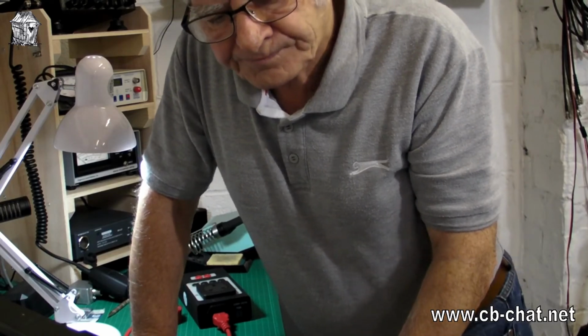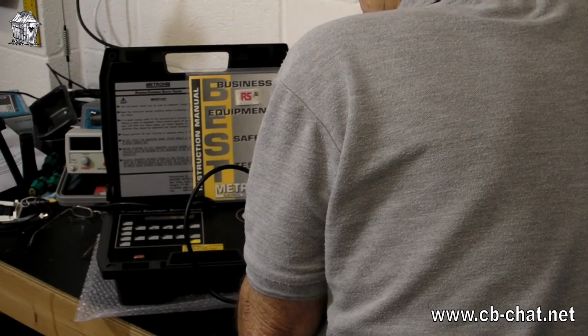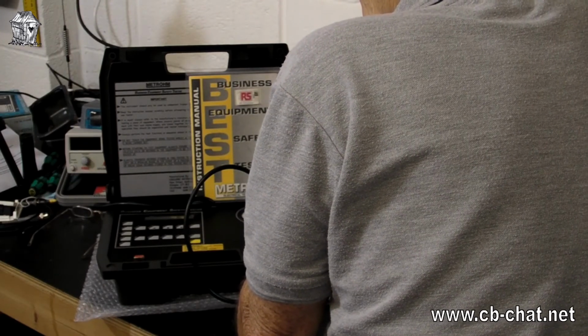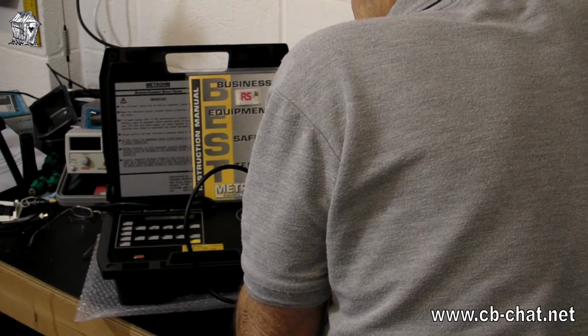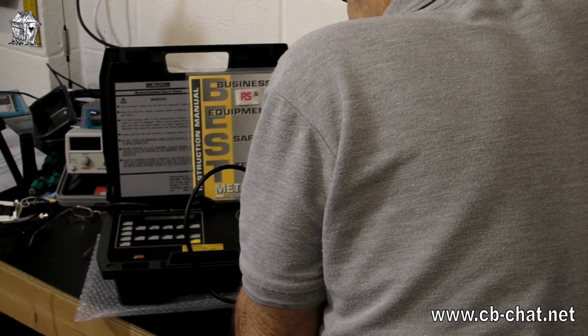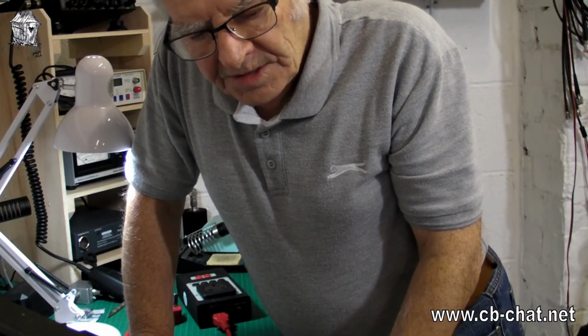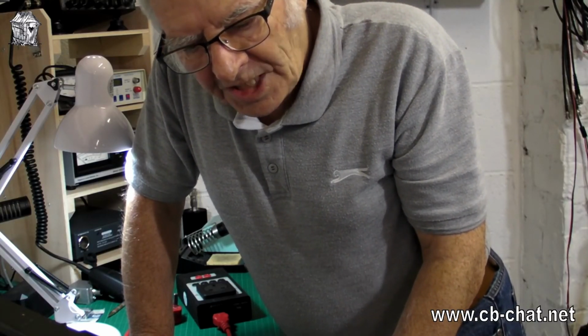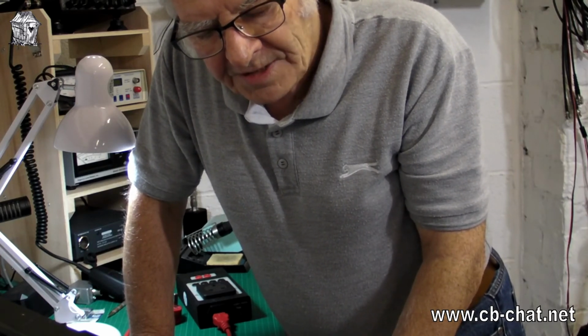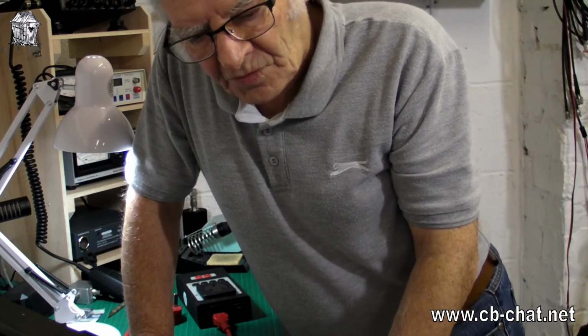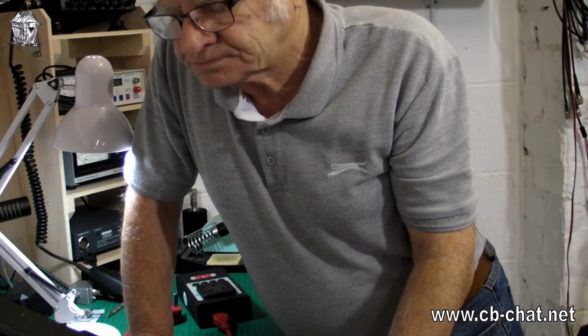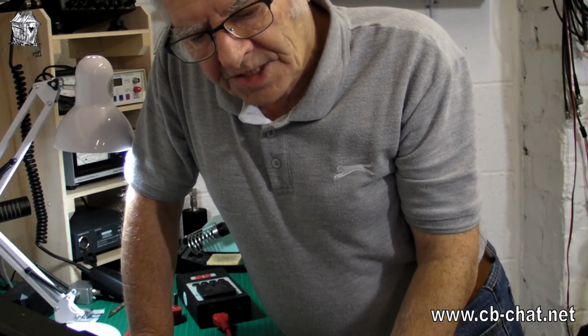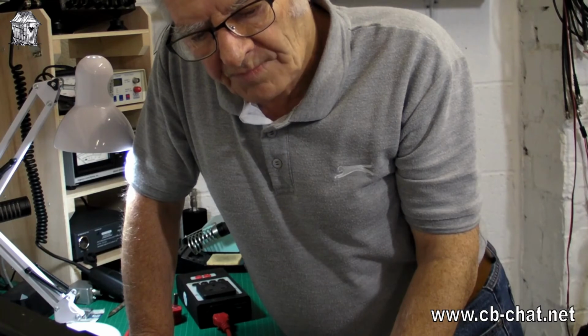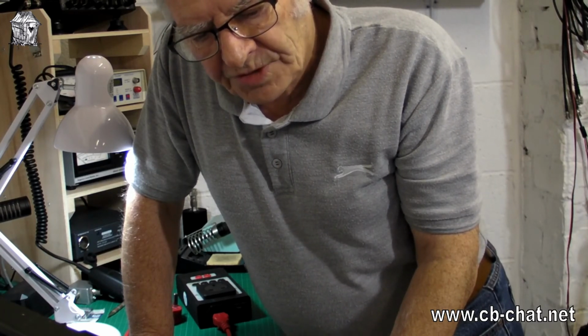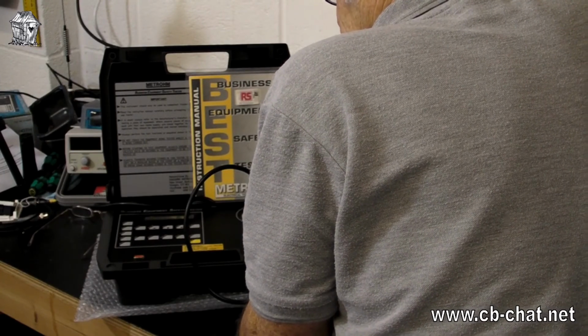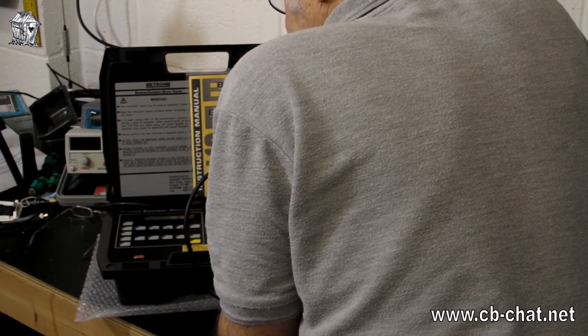Polarity testing. It's quite a slow tester, this. So it would take a while to do a full test on something, and it's just saying polarity testing at the moment, and then it will change over to say it's testing insulation testing. So it's tested the polarity. It's now saying insulation testing, which is of course putting 500 volts down the device. Again, taking a while. Come on. Oh, I could go and have a cup of tea while it's doing this, couldn't I? But of course polarity is okay, and insulation was okay.